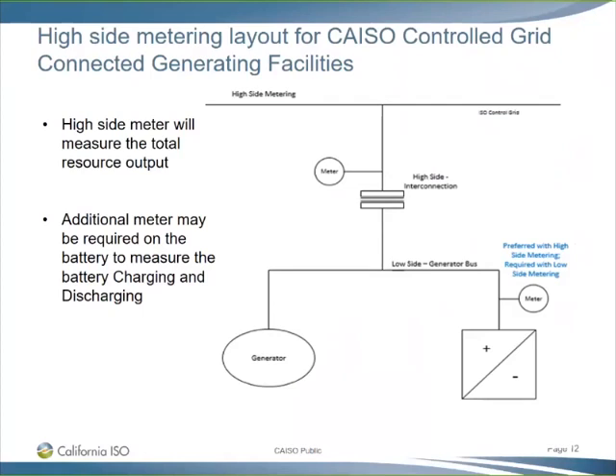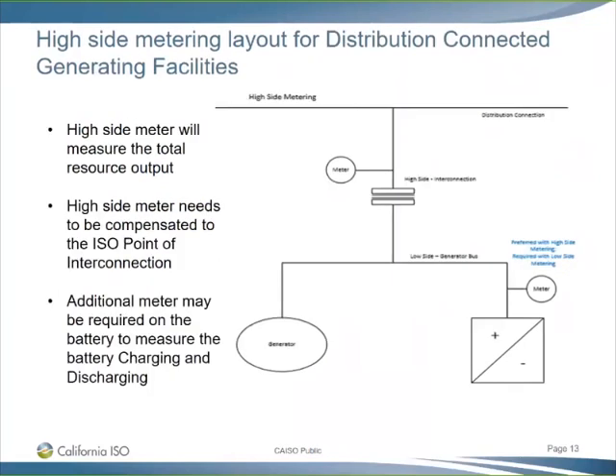In this case, where there is an on-site generator and a storage unit, and the resource is participating as a single resource ID, there is a high-side meter that calculates the net output. Then, for any additional metering purposes, the resource may require an additional meter on the battery to measure the battery charging and discharging. In the second scenario, where the resource is connected to the distribution level grid, the meter is again installed on the high side of the transformer, and an additional meter may be required to measure the battery charging or discharging. But since the resource itself is at the distribution connection, the meter needs to be compensated to the ISO point of interconnection.